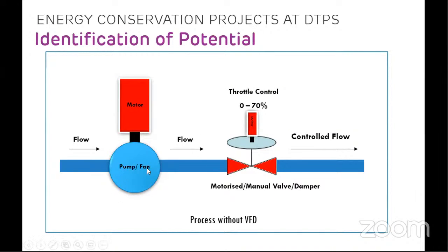Here we can see there is a process pump or fan, and the flow of the pump or fan, whether it is a fluid or air, is throttled using a valve. This is a motorized or manual valve or a damper, which is throttled from 0 to 70%, and the output flow is controlled. The full flow is not required by the process. Therefore, the flow is throttled. Now what happens is the motor is taking full rated power and the flow up to the valve is full, but the flow going after the valve is throttled. Therefore, the power is lost across this valve.